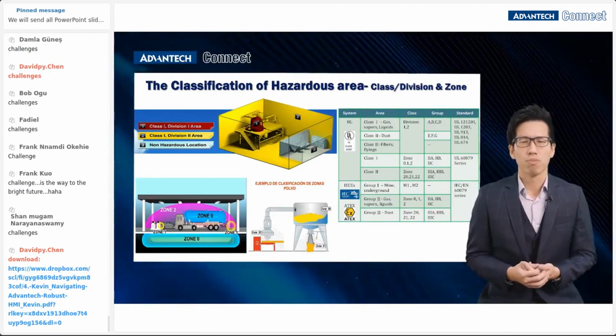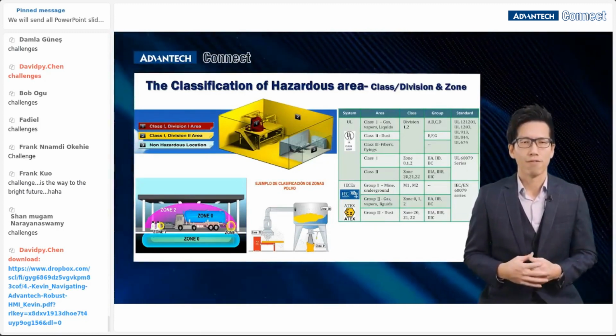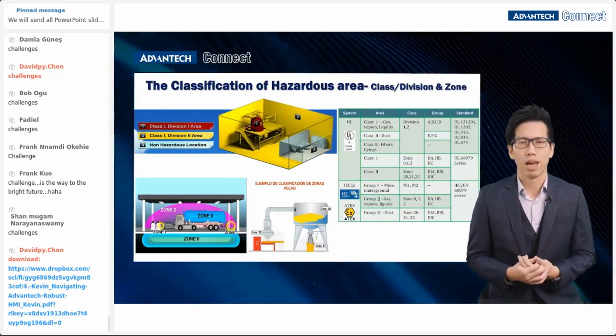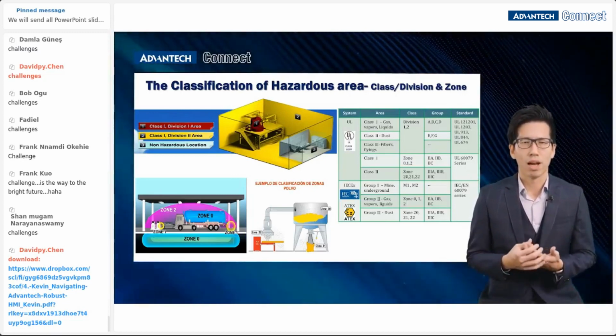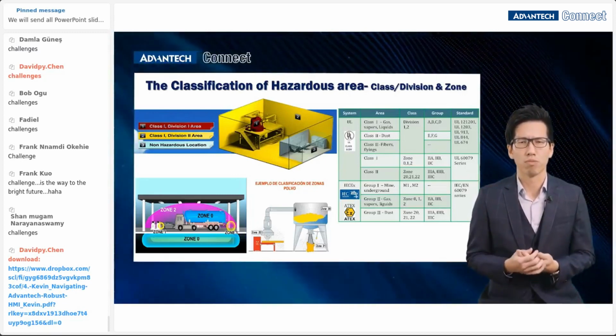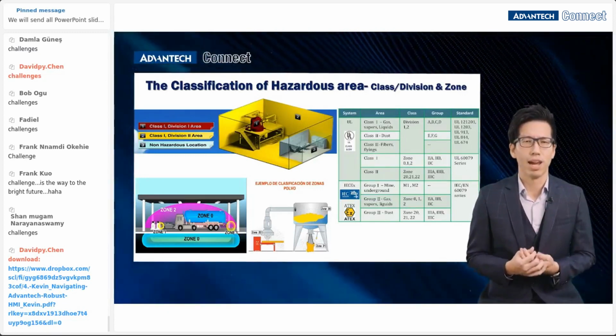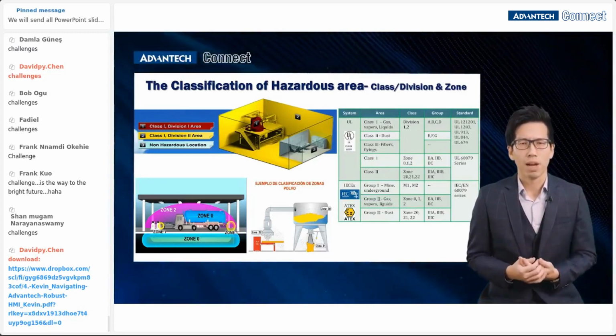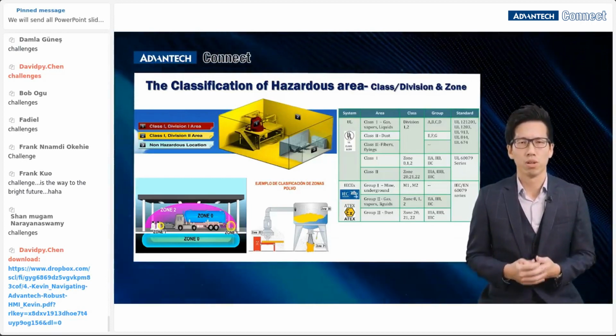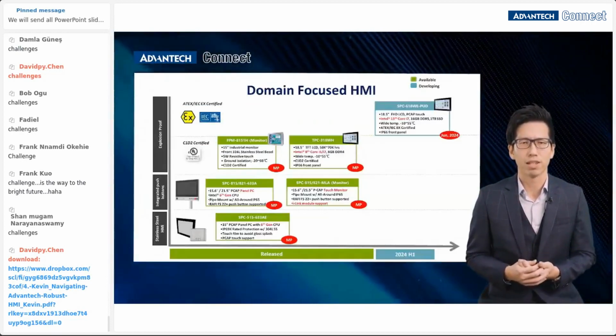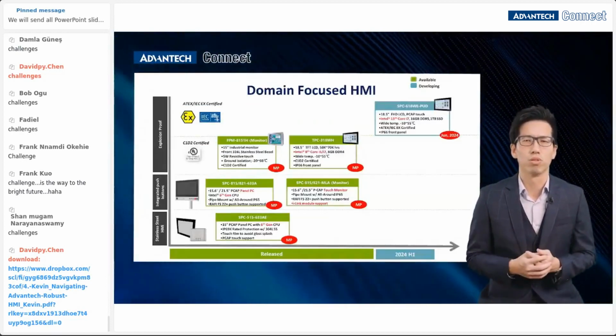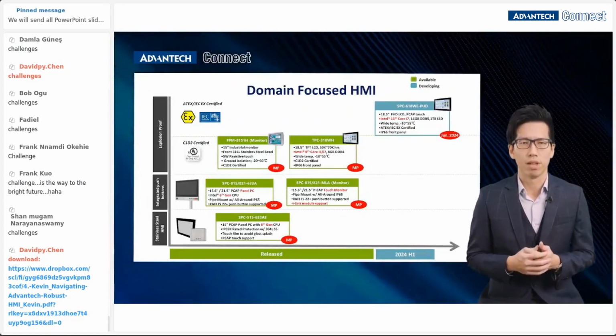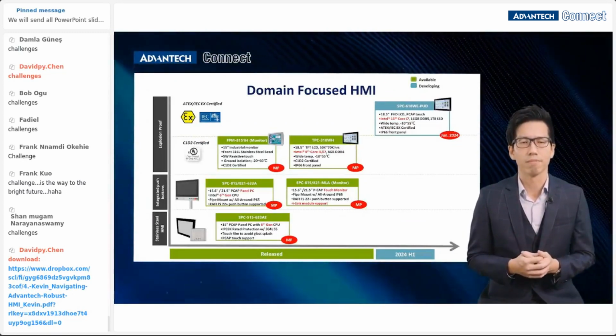All of the explosion-proof HMI apply to gas, vapor, and liquid areas, which means class 1 under UL regulation and group 2 under IECEX or ATEX. We only apply for division 2 or zone 2 class certifications, so we call it C1D2 or zone 2, which is different from other criteria we apply.